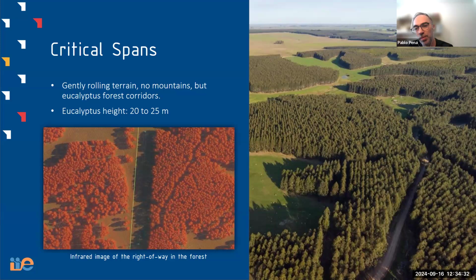Critical spans where wind is blocked are the major challenge for dynamic line rating from my point of view, as they can affect the line performance. Uruguay's terrain, defined by gently rolling hills and no mountains, seems perfect for dynamic line rating. However, we have extensive eucalyptus forests, as in the picture, that act as barriers, reducing the wind flow and consequently the cooling effect on the line. With eucalyptus trees reaching heights of 20 to 25 meters and taking into account that the conductor is at 7 to 15 meters high, this forest corridor can severely impact the efficiency of dynamic line rating by limiting the cooling provided by the wind.